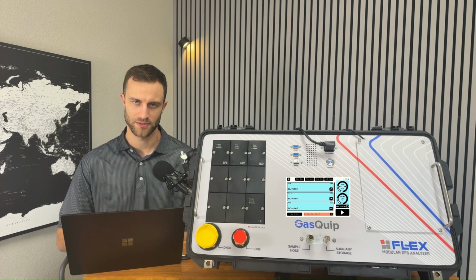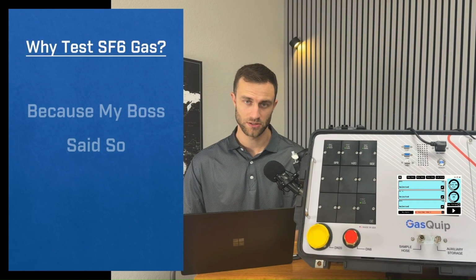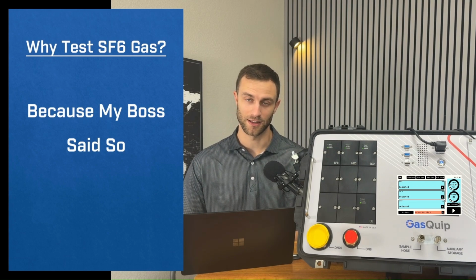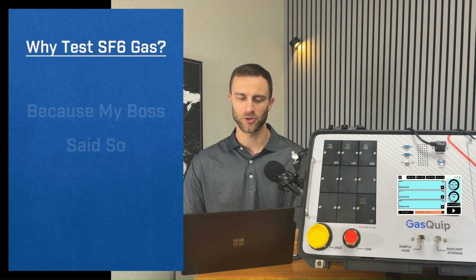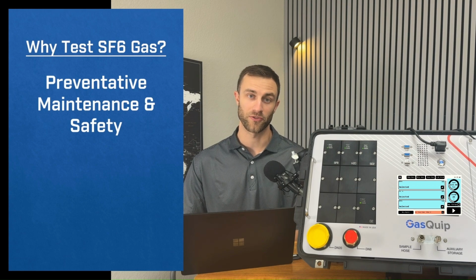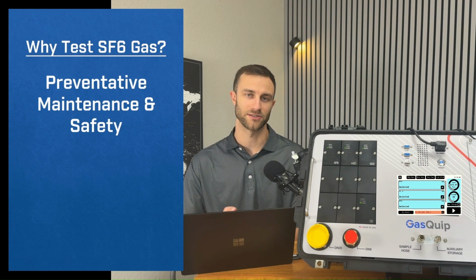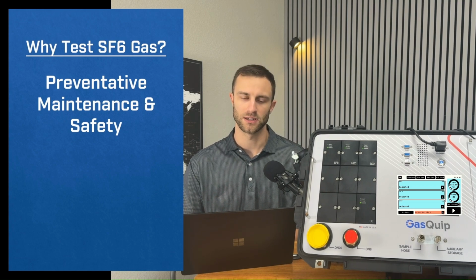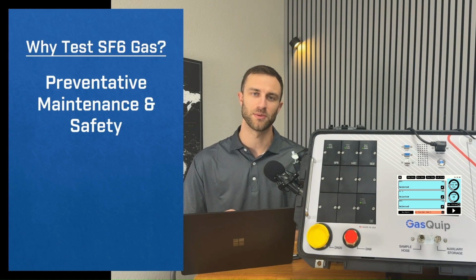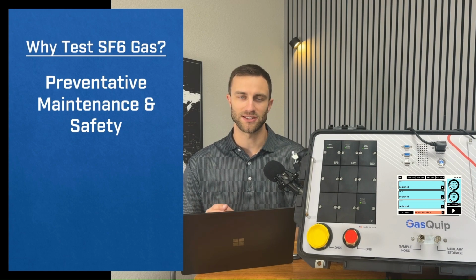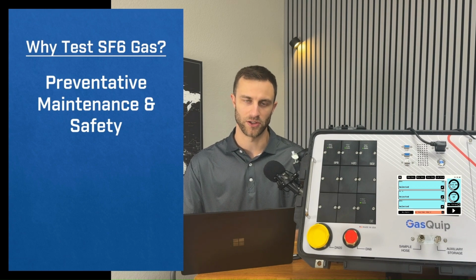Why do we test SF6 gas? Let's talk about that. The answer to this question is not because my boss said so. Although your boss may love to hear that, that is not really the reason. The real reason is for preventative maintenance and safety. So for preventative maintenance, the engineers that design the equipment that we will be testing, whether it's a circuit breaker or switchgear, gas insulated bus, they have set limits associated with contaminants or purity limits that need to be met in order to maintain the life of the equipment and realize the return on investment that you made in that equipment. So much smarter people than us, the engineers, the people who set the standards with the IEC, set these standards for a reason, and that is why we're measuring these individual values to get a picture of the health of the breaker and to extend its life ultimately.